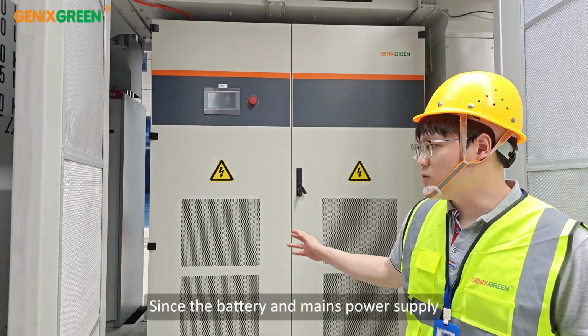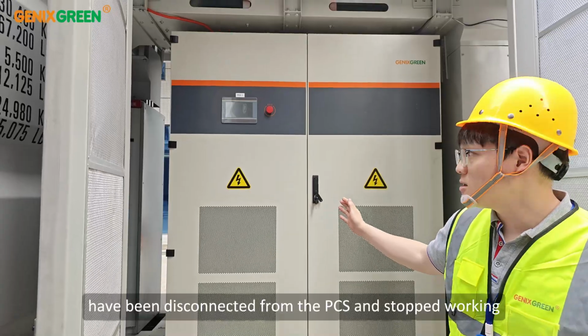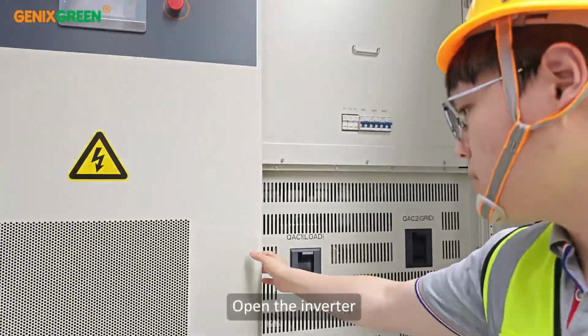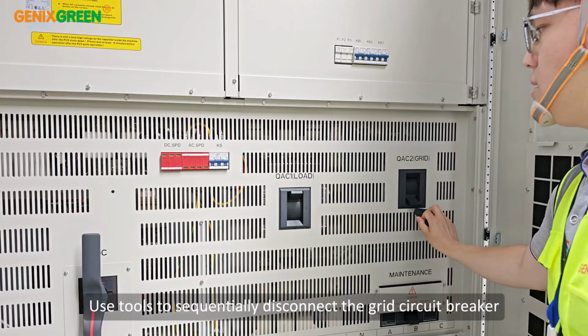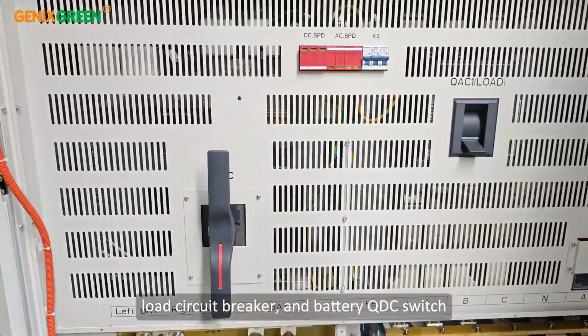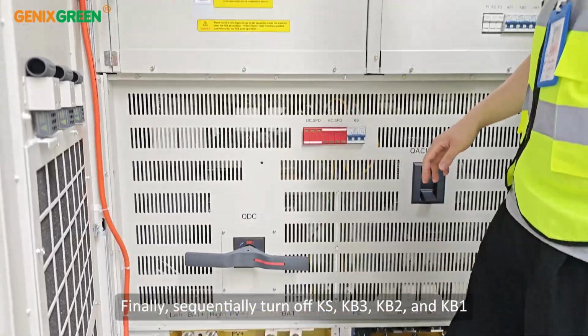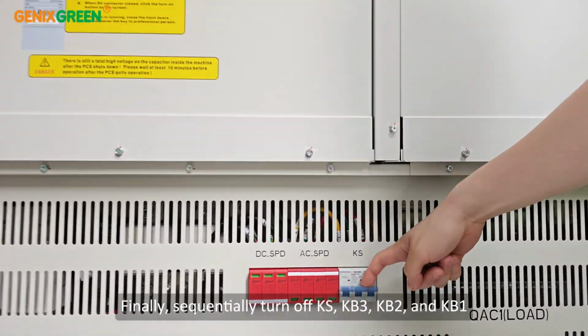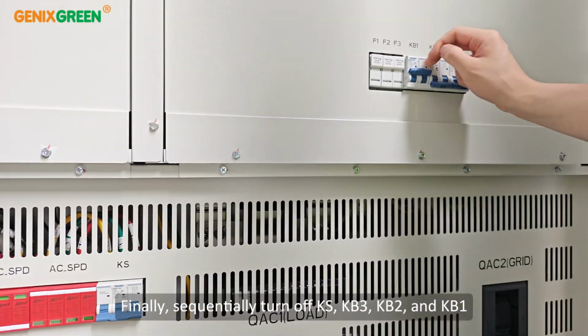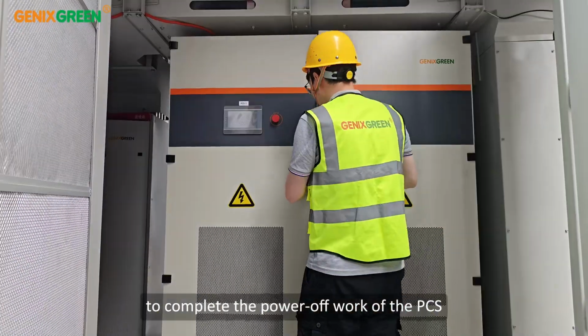Since the battery and mains power supply have been disconnected from the PCS and stopped working, open the inverter. Use tools to sequentially disconnect the grid circuit breaker, load circuit breaker, and battery QDC switch. Finally, sequentially turn off KS, KB3, KB2, and KB1 to complete the power off work of the PCS.